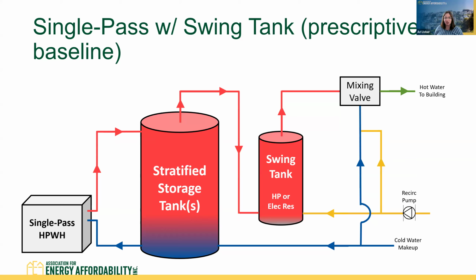As soon as somebody is going to use hot water and turn on their tap, then that hot water is drawn from the top of the storage tank, which again is always going to be the hottest. It comes through the swing tank. Now, the swing tank is not actually designed to be a source of primary heating. The water is already going to be really hot coming out of the top of the storage tank. The swing tank does have a heat pump or electric resistance element in there, but it's not actually doing the work of heating up water for delivery. So we're coming from the storage tank through the swing tank, still at 140 as an example, and then coming through the mixing valve here, where it's mixed with cold water and delivered to the building.